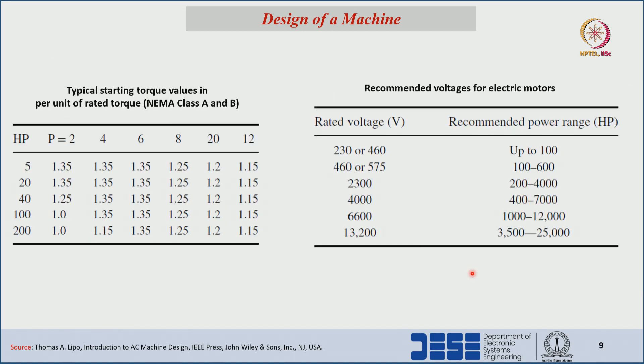Typical starting torque values per unit with respect to rated torque for NEMA class A and class B, for different poles and different HP ratings, can be found in the standards. These numbers are taken from NEMA, IEEE, or IEC standards. Recommended voltage ratings for electrical machines range up to 13 kV, with HP ratings up to 25,000 HP, including 230 V, 460 V, 2300 V, 4 kV, 6.6 kV, and 13 kV.